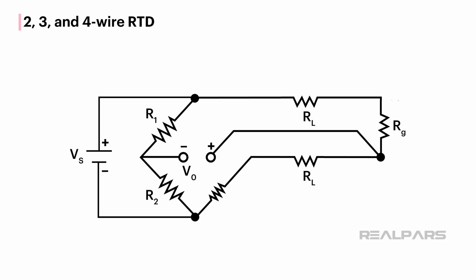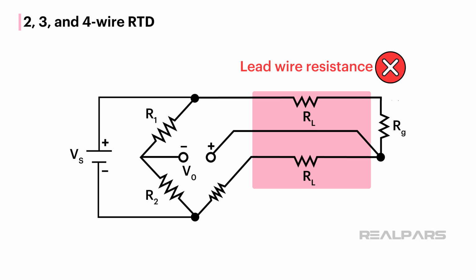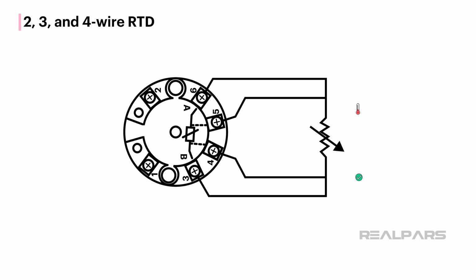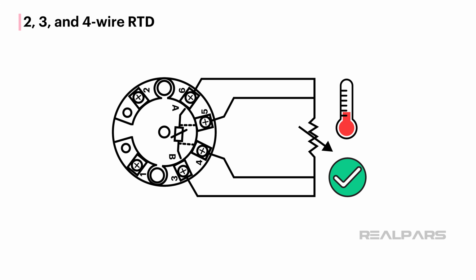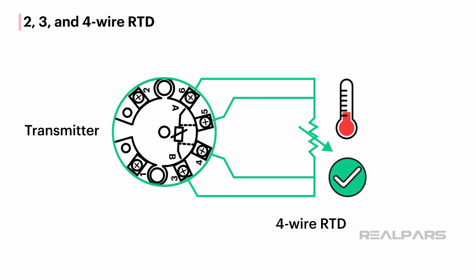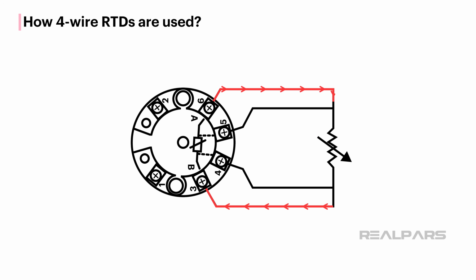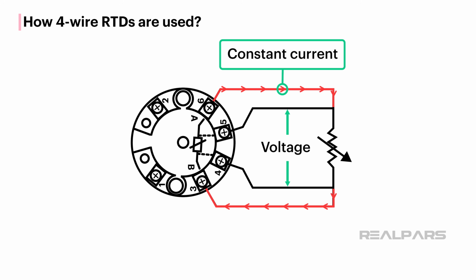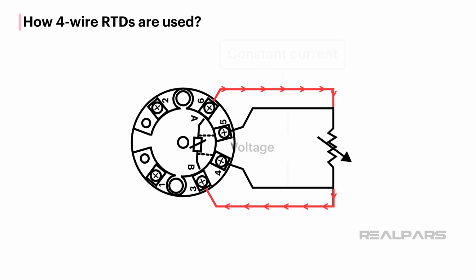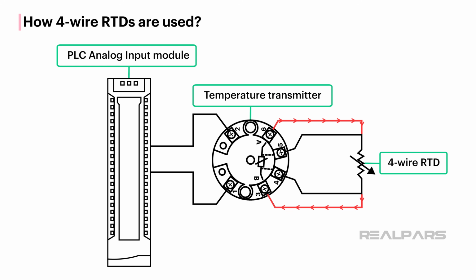Having a 3-wire RTD connected to a Wheatstone bridge eliminates the lead wire resistance problem. Probably the best and most accurate temperature measurement is made using a 4-wire RTD connected to a constant current source transmitter. The transmitter current is unaffected by the lead wire length. The voltage resulting from the constant current and the RTD temperature is detected by the transmitter. The transmitter converts this detected voltage and sends a corresponding signal to a receiving instrument, such as a PLC.